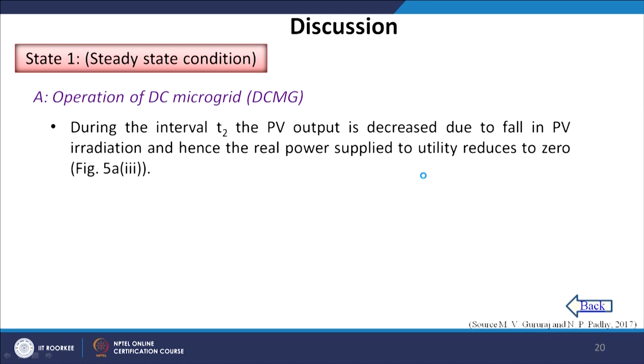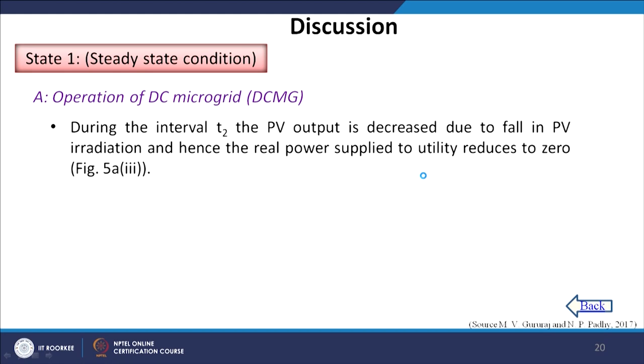During interval T2, the PV output decreases due to a fall in PV radiation, and hence the real power supply to the utility reduces to zero. During interval T3, there is a switching of additional DC load within the DC microgrid, and the deficit power is supplied by the utility grid. Despite all the switching dynamics, the controllers of various converters of the DC microgrid perform satisfactorily, and the DC grid voltage is regulated at 1200 V during all modes.